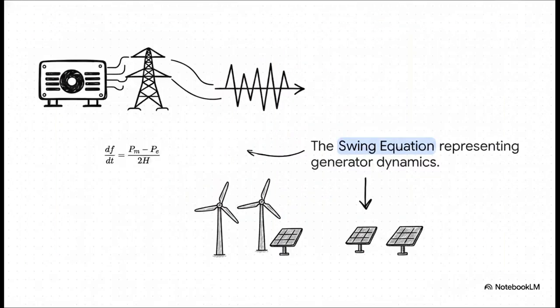And the literal, mathematical rules of the game for grid stability are defined right here by the swing equation for generator dynamics. See that H in the denominator? That represents the system's inertia. As we add more solar and wind, that H value drops, and because H is on the bottom of the fraction, as it shrinks, the rate of change of frequency, that df/dt over on the left, gets larger and faster. Basically, the grid becomes highly vulnerable to sudden, violent frequency disturbances.